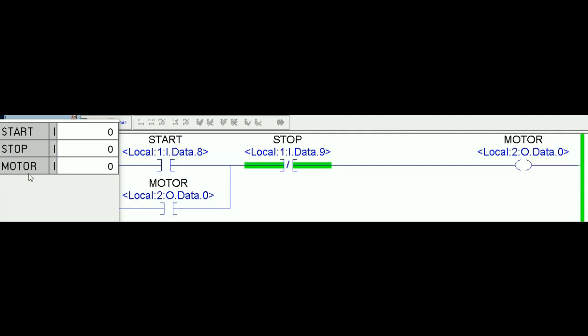When the operator pushes the start button, it is read as one in PLC memory, so the XIC referring to start shows true. Logic continuity exists and the motor turns on. As long as you hold start, the XIC referring to start remains true. When you release it, start goes back to open and the XIC goes false — but this does not turn off the motor because the latch is in place. The XIC referring to motor is now true because the motor is in the on state (logic one).